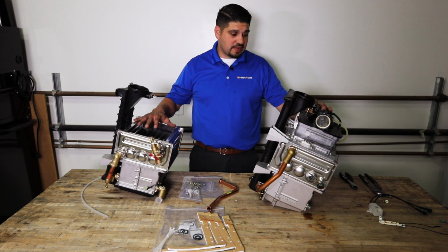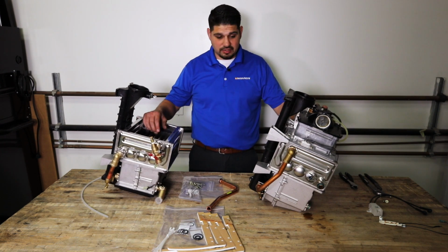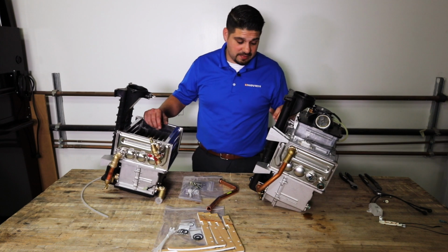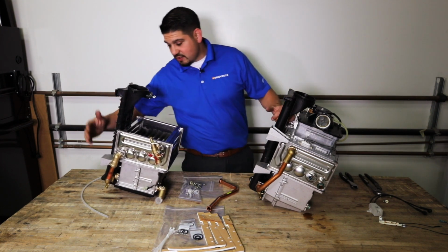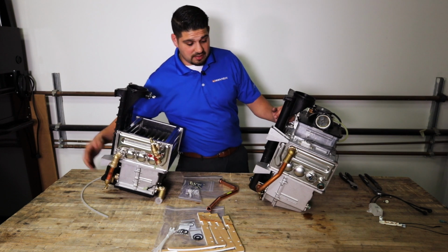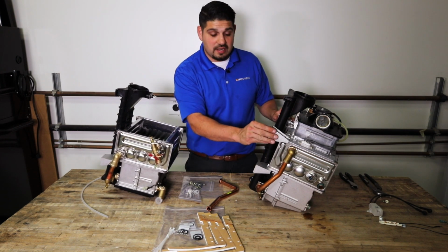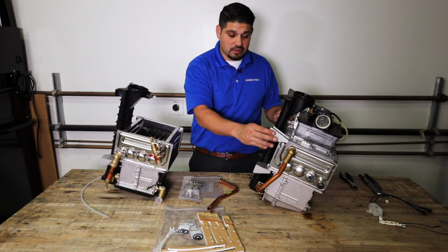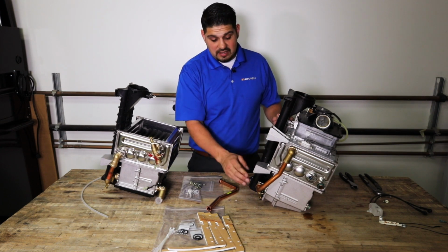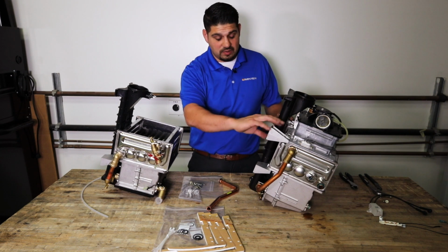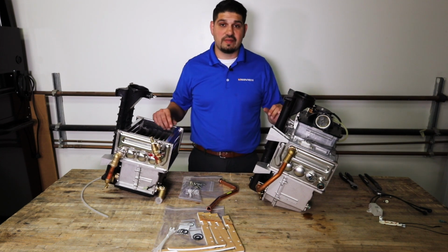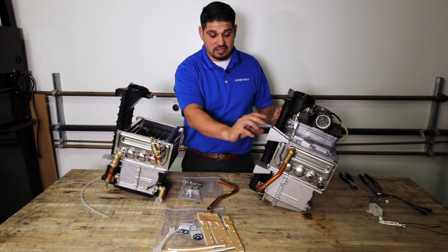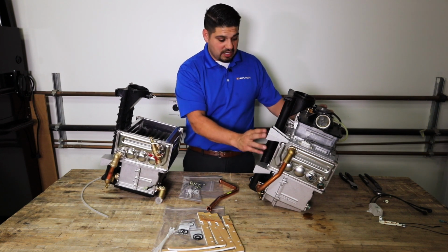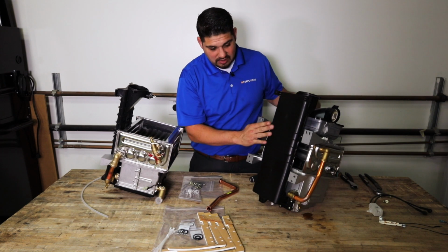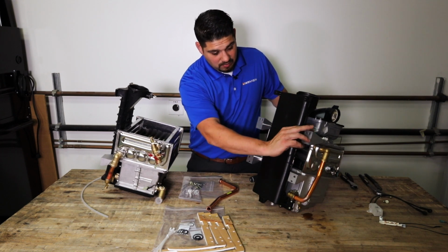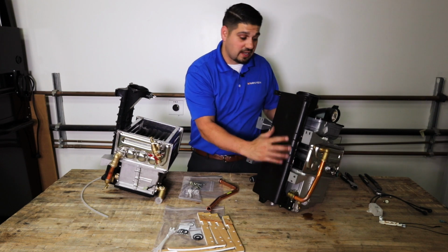Now we're ready to just about transition over our burner to our new heat exchanger. Some of the things you want to take into mind here is this heat exchanger is only going to come with the lower mounting brackets here. The upper two mounting brackets that we're going to need later on, we're going to have to transition those over. So be very careful and take into mind the angle and the position. So you don't put this on the opposite side, and then once you're putting everything back together, they're not going to work because the bolt holes aren't going to align. So make sure, and see if I can show you on this one here. See the two holes on the upper side. If you were to put this on this side, the holes will be on the bottom side. They're not going to align later on in the cabinet.